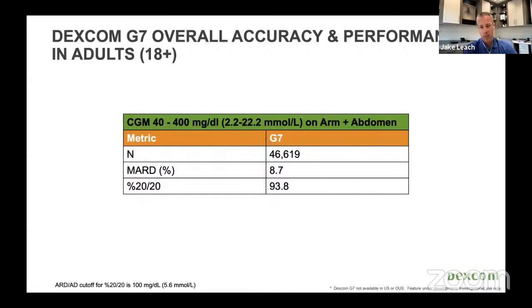What I tend to pay much more attention to are metrics like percent 20/20. That's generally the number of points that are within 20% of the reference when glucose is above 100 milligrams per deciliter. When it's below, it's 20 milligrams per deciliter. And the idea there is that if you're off by more than that, you might make a different clinical decision. And the farther off you go, if you're off by 40%, then you're probably making the wrong decision. So those are the metrics that I pay the most attention to, because those are the ones that tell you how well the device performs.